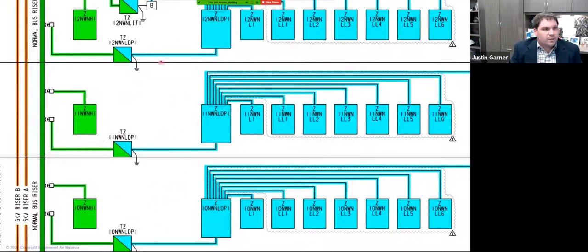All right, we're going to move down the building now, and this is a high-rise building. This is pretty typical. So all the electrical rooms are stacked on top of each other as you go up the building. And so they use this bus riser, which is just a very large conductor that can be used to distribute power throughout the building. And in this particular case, this riser ran vertically up through all the electrical rooms, and it has plugs that plug into it. So that's what you see right here. And then coming off of that is additional distribution panels.